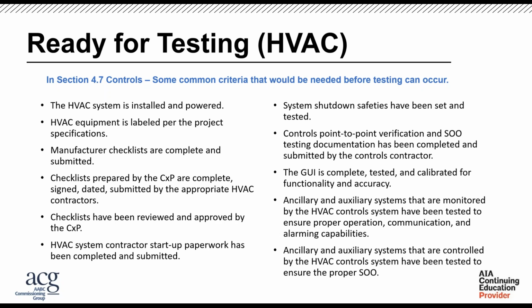We're verifying those connections. You also want to make sure that the manufacturers' checklists and all of those are completed as well. You want to make sure your head-end unit and your system, the redundancy, anything with the controls is there and available. And like I said, I've dealt with companies that will not install the head-end unit until there's dedicated space to house the server and the workstation has a lockable door. So these are challenges that we want to make sure are addressed prior to ready for testing.